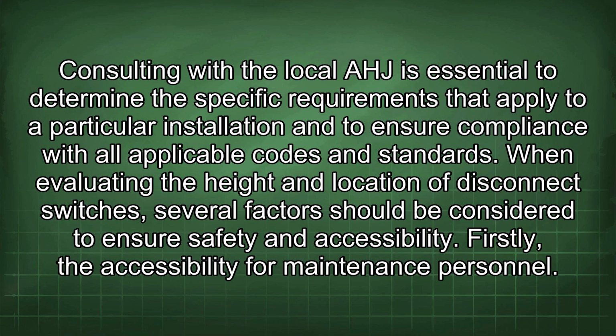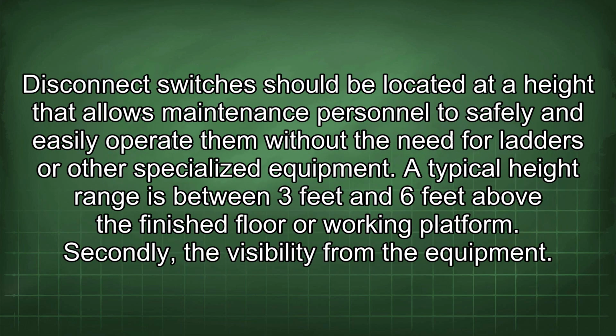When evaluating the height and location of disconnect switches, several factors should be considered to ensure safety and accessibility. Firstly, the accessibility for maintenance personnel. Disconnect switches should be located at a height that allows maintenance personnel to safely and easily operate them without the need for ladders or other specialized equipment. A typical height ranges between 3 feet and 6 feet above the finished floor or working platform.